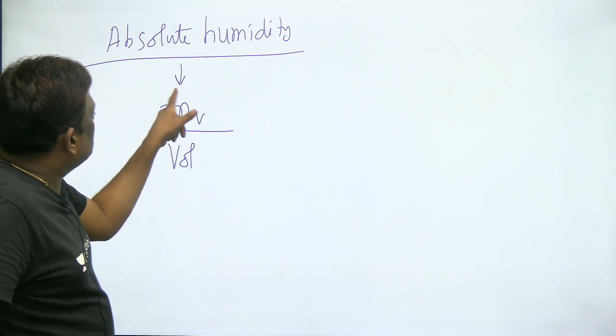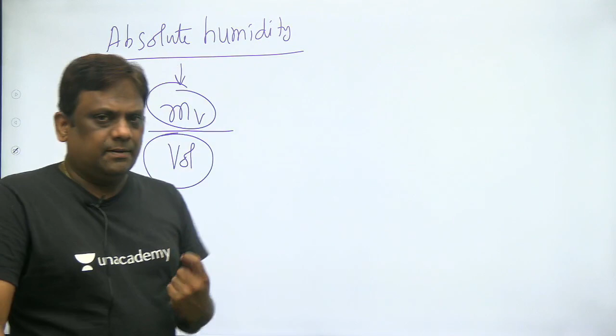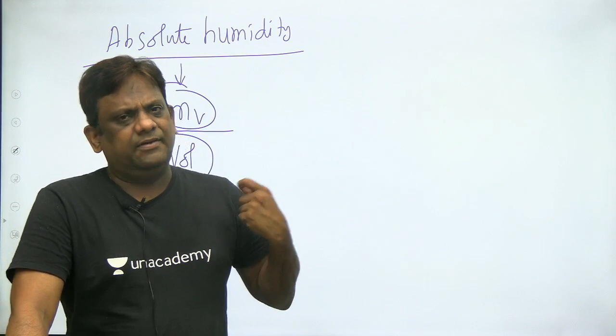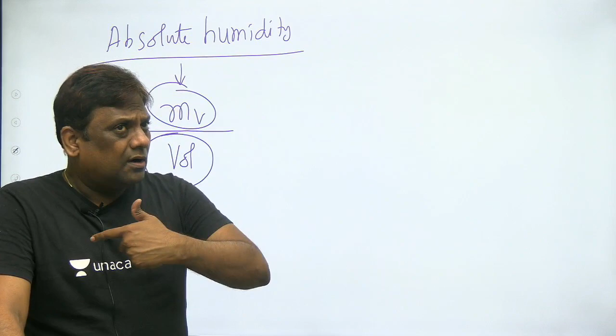The first psychrometric term that we have seen is specific humidity or humidity ratio, but some people loosely use it as absolute humidity, though strictly absolute humidity is nothing but the mass of vapor in a certain volume of air. Keep in mind that omega is a function of partial pressure of vapor only. As long as omega remains the same, PV remains the same, they are interlinked. So when I start developing the psychrometric chart, I'll be using this condition predominantly. What omega physically represents is very, very important.